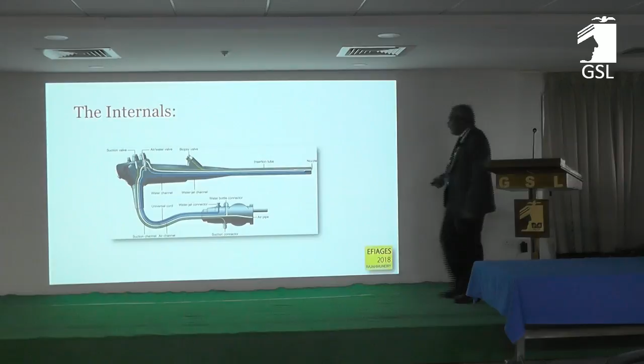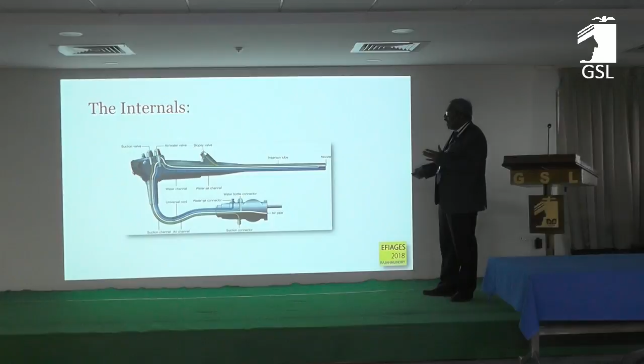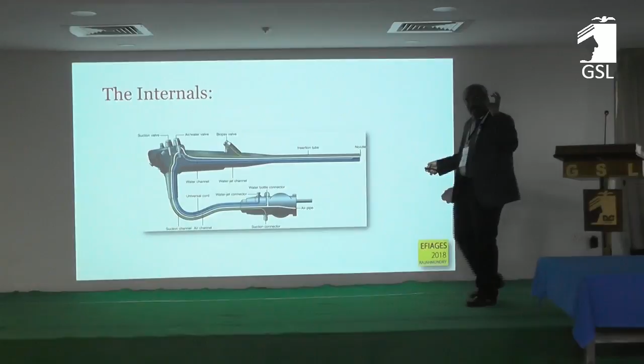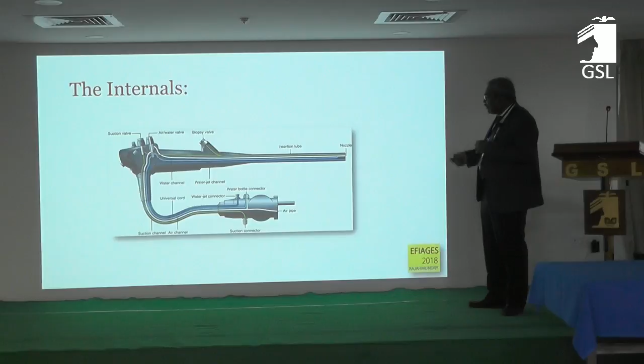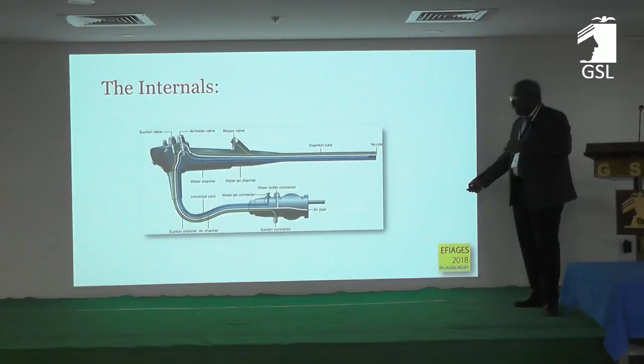This is the internals. You can see the three colored lines running through almost the entire scope. These valves control the movement of air, water, and the degree of suction. The biopsy valve has an adapter over it, so it does not affect the air and suction passing together. At the end you have a separate air pump and a separate water bottle which run together, and apart from that a separate suction connector which is independent of the processor. You need a separate suction unit, and all the other optical gadgets are always associated.